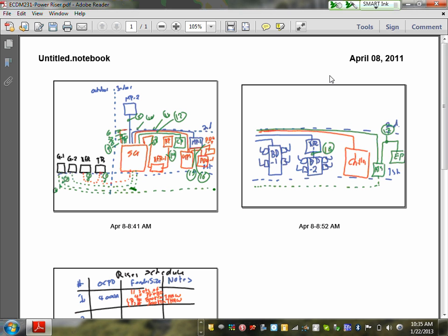Once you do that, this is bonded. This is not a separately derived system at that point, because it's getting its ground and its neutral reference from the service gear over here. At that point, this can be a three-pole transfer switch. When you put them in the switch gear, if it's a separately derived system, you're going to end up with four-pole circuit breakers. Yep. It'll be expensive.